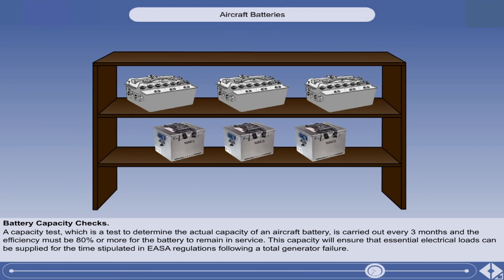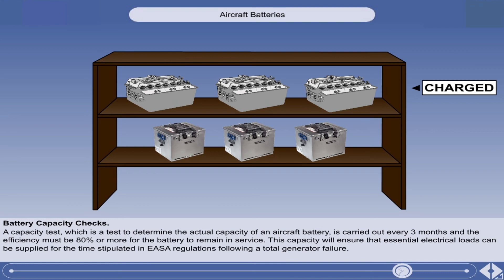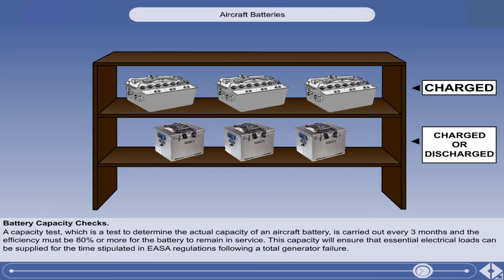Spare batteries will be held ready for use in the electrical workshop. Lead acid batteries are stored in a charged state to prevent deterioration of their plates. NICAD batteries can be stored in a discharged state with no detrimental effect to the battery, and therefore have a longer storage life or shelf life.